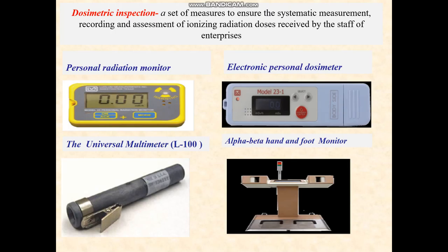The electronic personal dosimeter is a compact and lightweight pen-type personal dosimeter. It is ideal for the measurement and general monitoring of gamma and X-ray radiation in medical and laboratory environments, as well as any controlled or restricted area where personal radiation monitoring is required or desired.